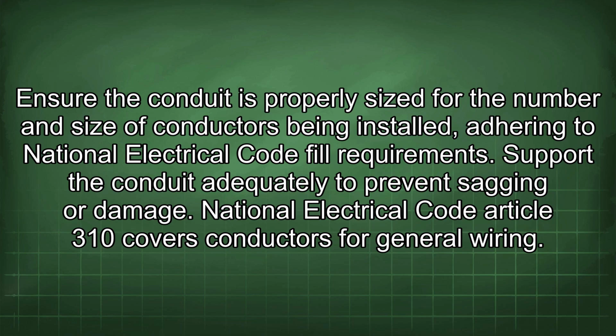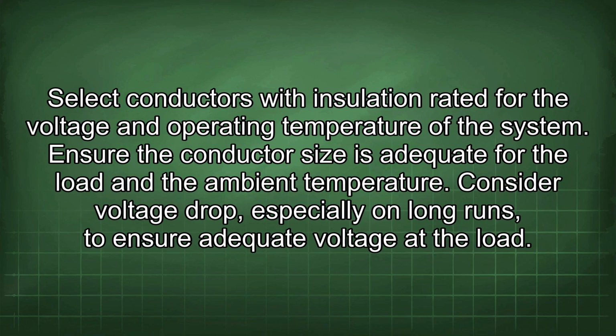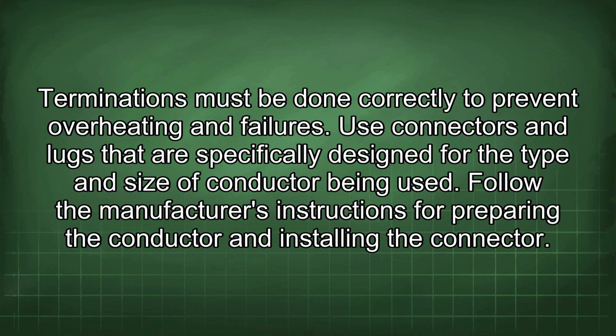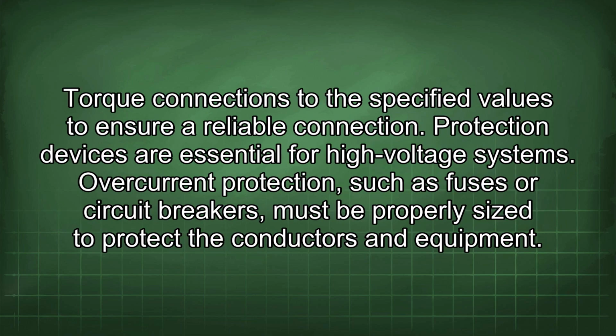National Electrical Code Article 310 covers conductors for general wiring. Select conductors with insulation rated for the voltage and operating temperature of the system. Ensure the conductor size is adequate for the load and the ambient temperature. Consider voltage drop, especially on long runs, to ensure adequate voltage at the load. Terminations must be done correctly to prevent overheating and failures. Use connectors and lugs that are specifically designed for the type and size of conductor being used. Follow the manufacturer's instructions for preparing the conductor and installing the connector. Torque connections to the specified values to ensure a reliable connection.